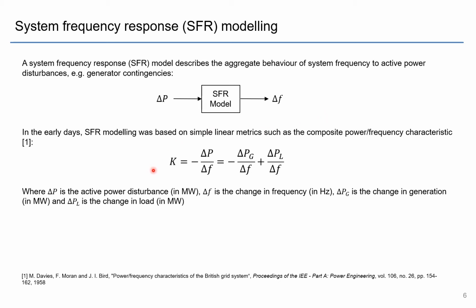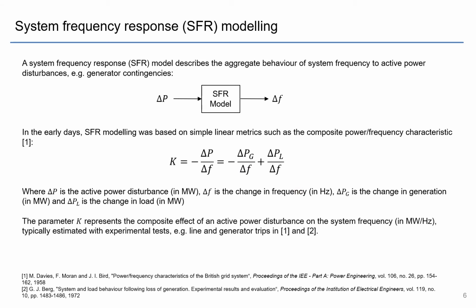And you can see it is a characteristic K, which is basically delta P divided by delta F. So you have a change in active power, which is the disturbance. You have a change in frequency, delta F, and you can break it down further: you have a generator component, a change in generation, and then you have a load component, or a change in load. And so this was beta and alpha back in the day. So the parameter K actually represents the composite effects of an active power disturbance on the system frequency, and is measured in megawatts per hertz. So if you gave an injection of, say, 100 megawatts, and you had 100 megawatts per hertz, then you would get a 1 hertz change in frequency as a result.